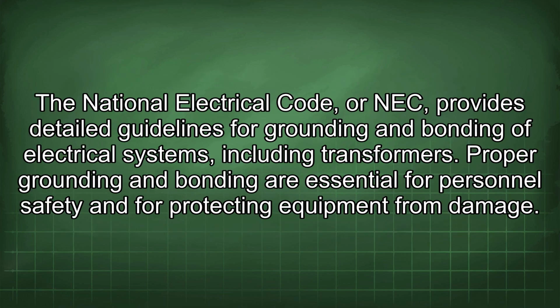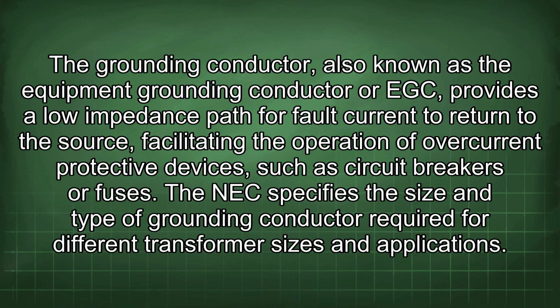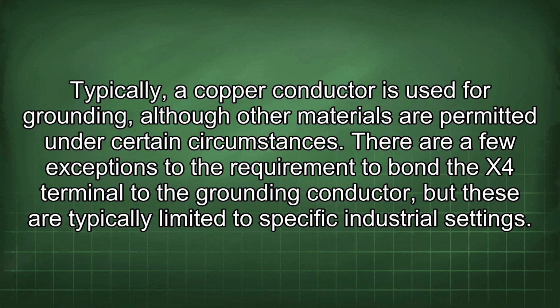The National Electrical Code, or NEC, provides detailed guidelines for grounding and bonding of electrical systems, including transformers. Proper grounding and bonding are essential for personnel safety and for protecting equipment from damage. The grounding conductor, also known as the equipment grounding conductor or EGC, provides a low impedance path for fault current to return to the source, facilitating the operation of overcurrent protective devices such as circuit breakers or fuses. The NEC specifies the size and type of grounding conductor required for different transformer sizes and applications. Typically, a copper conductor is used for grounding, although other materials are permitted under certain circumstances.